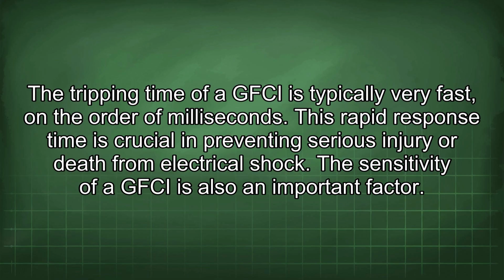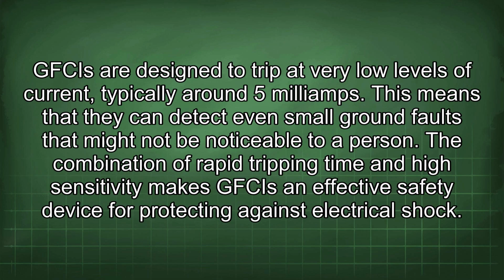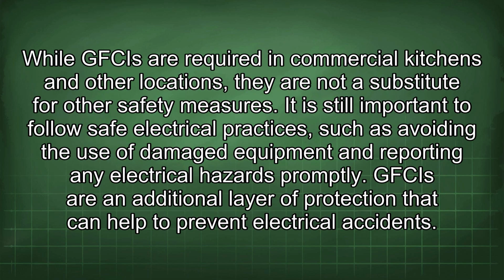The sensitivity of a GFCI is also an important factor. GFCIs are designed to trip at very low levels of current, typically around 5 milliamps. This means that they can detect even small ground faults that might not be noticeable to a person. The combination of rapid tripping time and high sensitivity makes GFCIs an effective safety device for protecting against electrical shock. While GFCIs are required in commercial kitchens and other locations, they are not a substitute for other safety measures. It is still important to follow safe electrical practices, such as avoiding the use of damaged equipment and reporting any electrical hazards promptly. GFCIs are an additional layer of protection that can help to prevent electrical accidents.